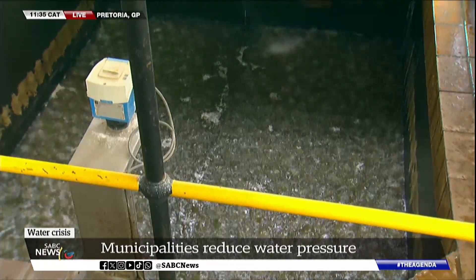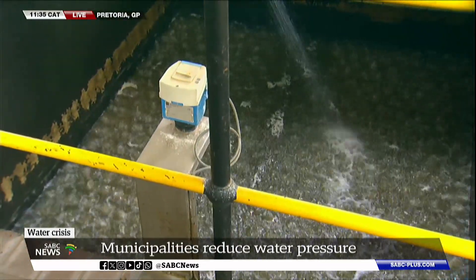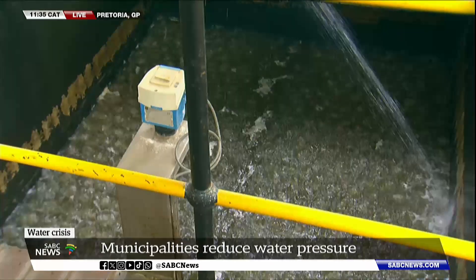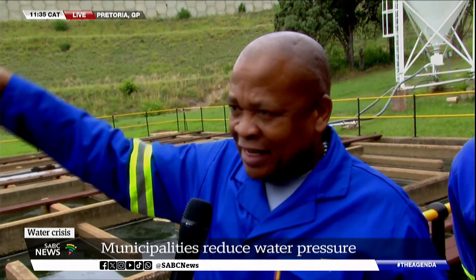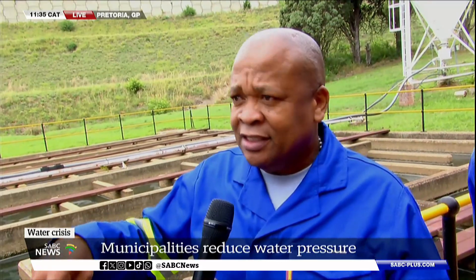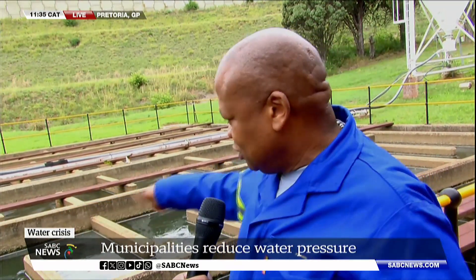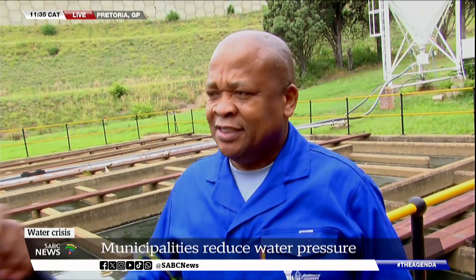We started off at the dam and essentially water from the dam lands up here. Basically, the reason for this facility is to augment water supply and reduce over-reliance on rainwater. Water comes in through that point by gravity feed into the dosing point, where we add chemicals — specifically flocculant. As it goes through this channel, the water mixes with the flocculant so it can form particles, and it moves into the flocculation channel into the main building.